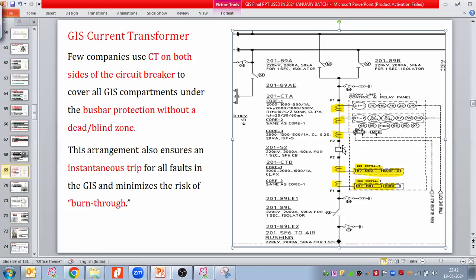We are taking CTs on both sides of the breaker. On the upper side, the CT with 3 cores is for line distance protection 1, line distance protection 2, and metering. And on the bottom of the breaker, we are taking the CT which is responsible for the bus bar protections: 87, 50BF breaker failure protection, bus bar protection and bus bar protection 2. Now what will happen if any fault happens once you close the disconnector, between here and the breaker contact? Now there is no blind zone.